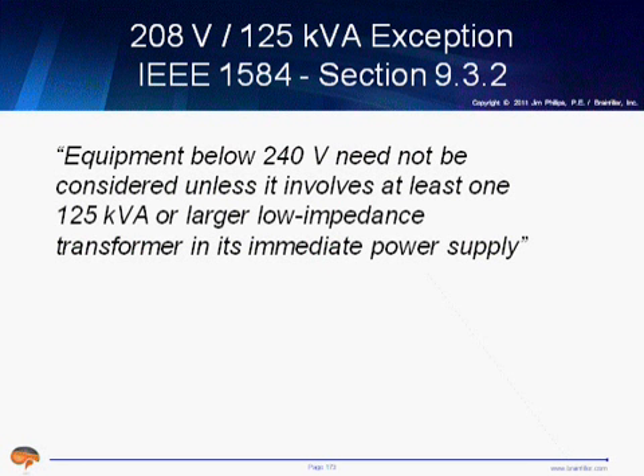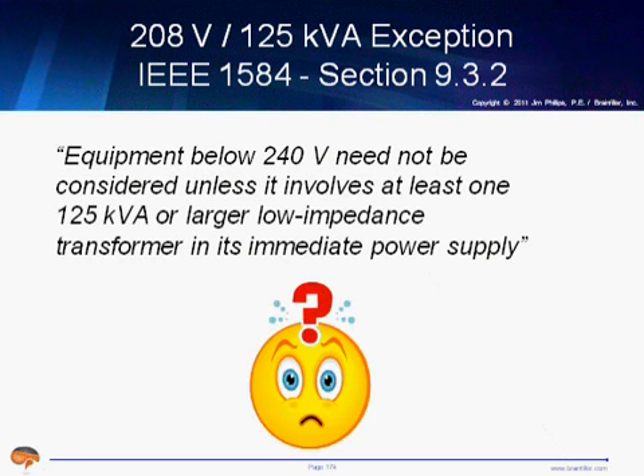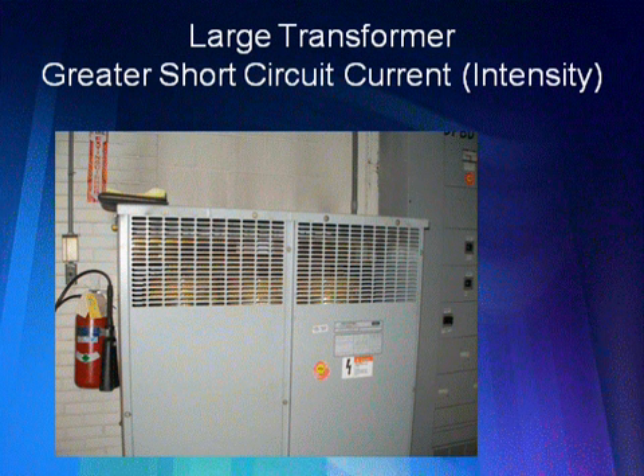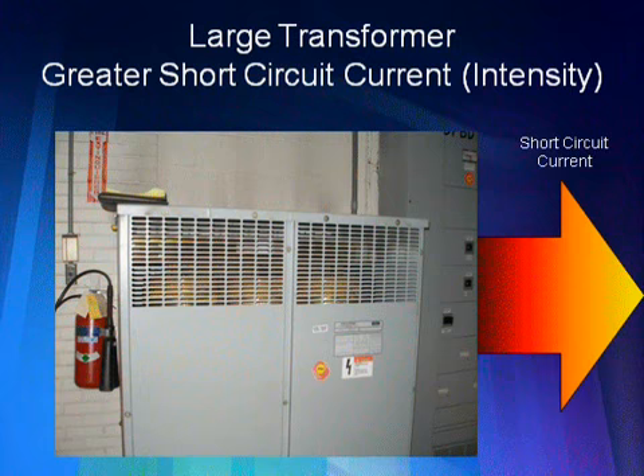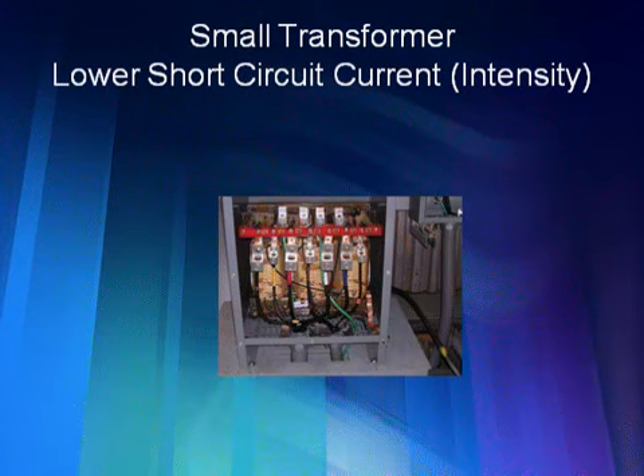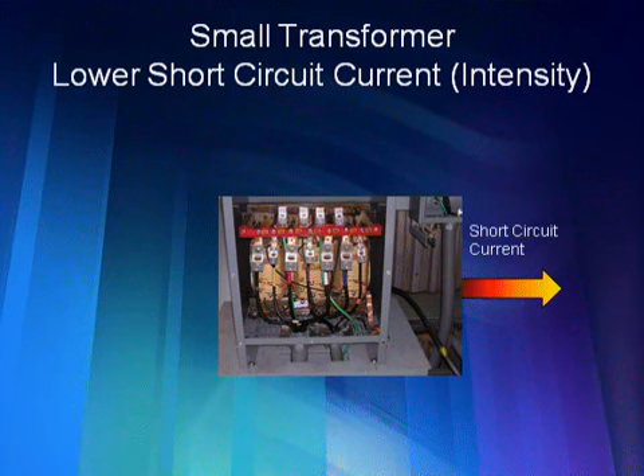IEEE 1584 had some language that equipment below 240 volts doesn't need to be considered as part of the study, and below a 125 kVA transformer. 125 kVA was actually implying a 112.5 kVA transformer, and below 240 was implying 208 volts. Part of the reasoning behind this was that when you have an arc flash at lower voltage and lower current, it's not always easy to get it to sustain. The transformer size was originally used because if you have a short circuit on the secondary side of larger transformers, you have more current, more intense, as I called it earlier. And if you have a short circuit on the secondary side of a smaller transformer, the short circuit current tends to be lower.